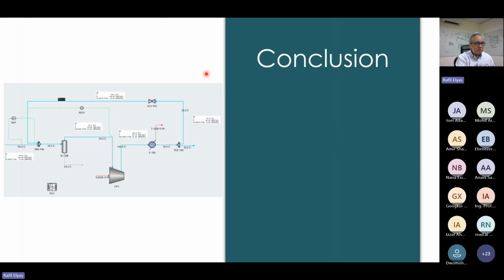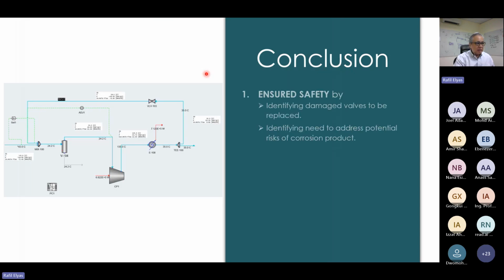Because that compressor was in recycle, that's why we saw the other symptom, which was suction header flaring. Because of the recycle, the suction header increased in pressure, and we had continuous flaring.